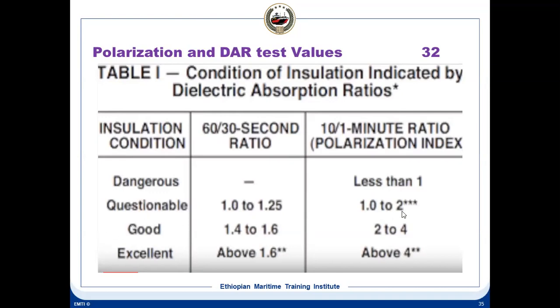Questionable, it is 1.0 to 2. It's questionable. But from 2 to 4 is also good, and above 4 is excellent. So if you apply a polarization index test and your value is falling in this range, that means your winding is not good. So what are the options to do further? You need to revarnish the winding, heat up the winding and check again whether it is coming up or not. If it is not coming up, then it has to be rewound.